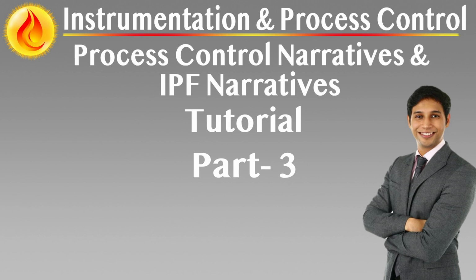Signal flows and control relationships. Outlines how signals, digital, analog, or communications, pass between subsystems during different phases of operation, such as startup sequencing and permissives, load control and transitions, shutdown and trip handling. Each signal is described by its role, e.g. start command, status feedback, interlock, its direction, and its participating systems. Modes of data exchange, e.g. hardwired I/O, Modbus TCP, OPC UA, are also identified.